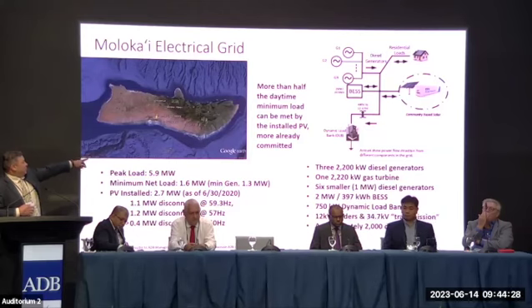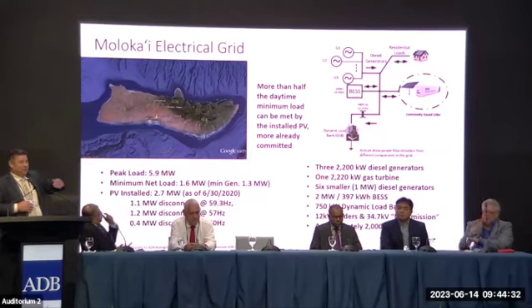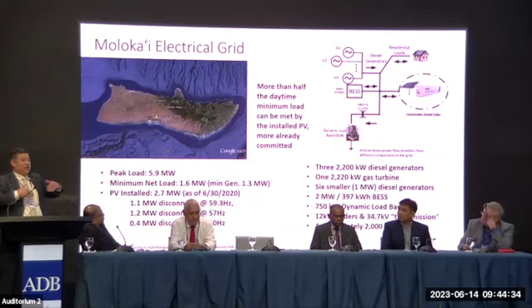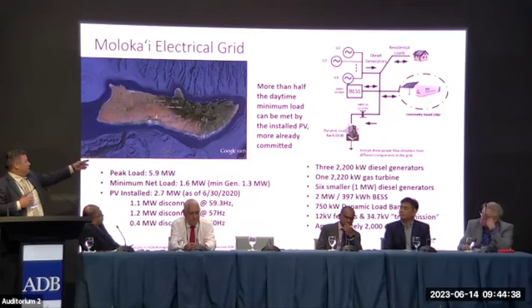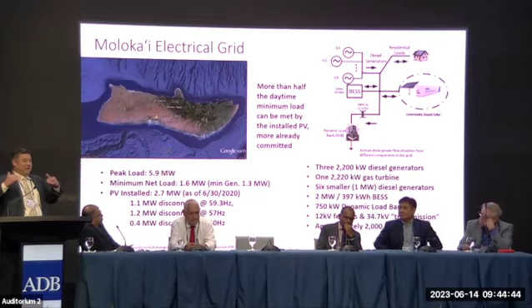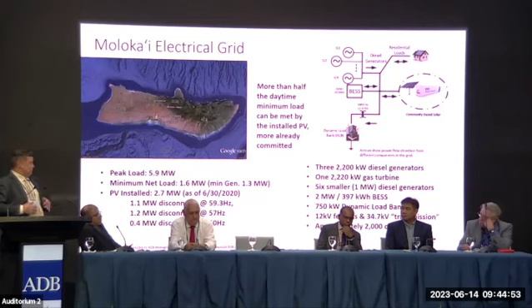The other thing we did, just a side note, was put in a dynamic load bank, because at times there was a risk that the solar would drive the generators down below their minimum point. So the university helped put this load bank in just to give them a cushion. They've never actually used it yet, but it gives the operators another tool in their belt - if there's a low load day and a high solar day, they have a tool to deal with it.